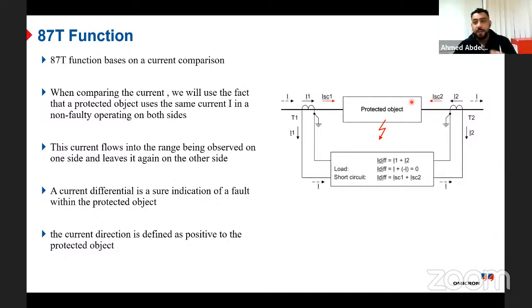If I use the very basic definition of the differential current, it is the absolute value of the vectorial sum of all currents in and out. So I have a diff in a stable condition, where I1 is equal to I2, and we will ignore the losses in our system. So I diff, in case of normal load or external fault, will equal I plus in bracket minus I. So overall, it will be equal to 0 in a stable condition.